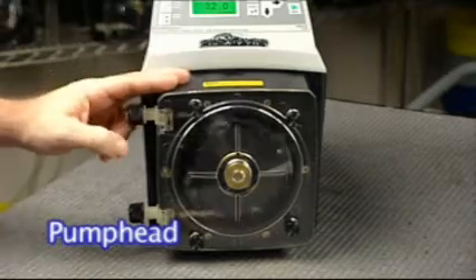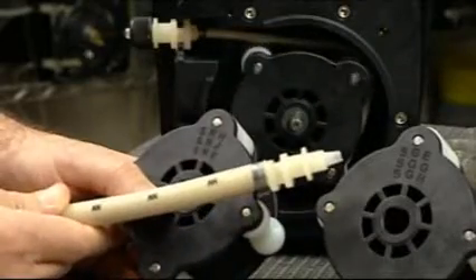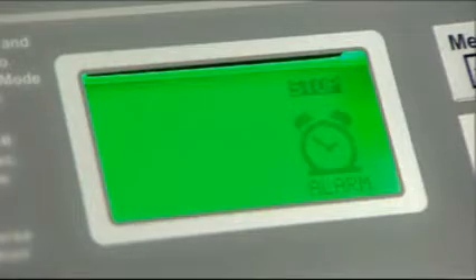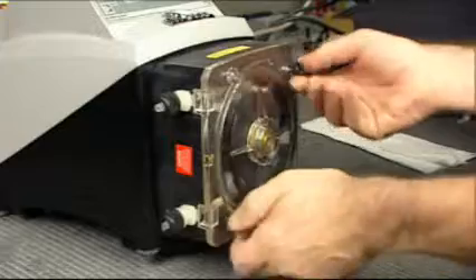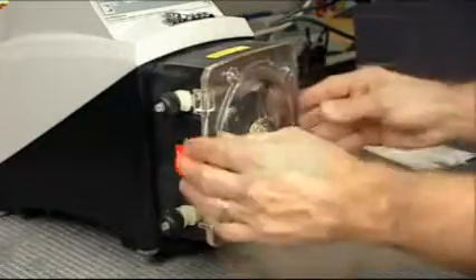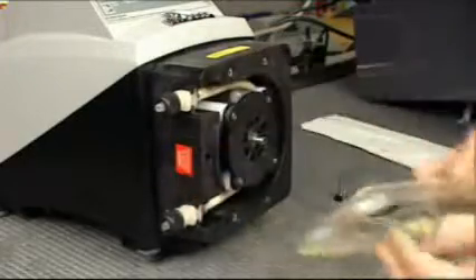The pump head assembly encloses the pump tube assembly, the roller assembly, and the tube failure detection system sensors. Remove the 4 thumb screws to remove the pump head cover and access the pump head.